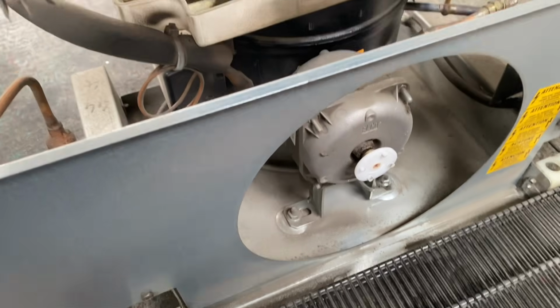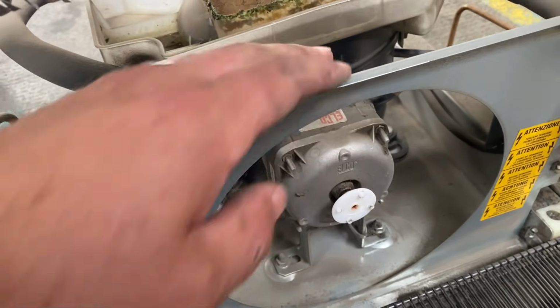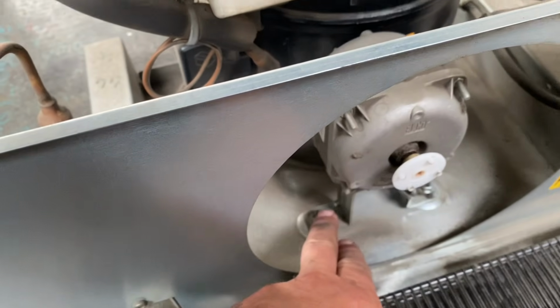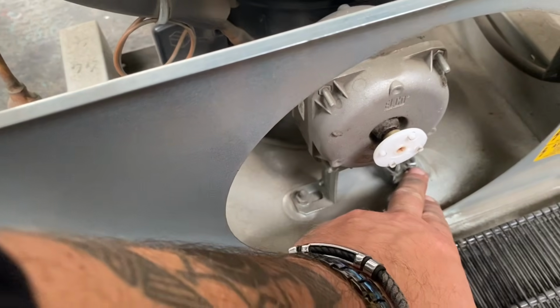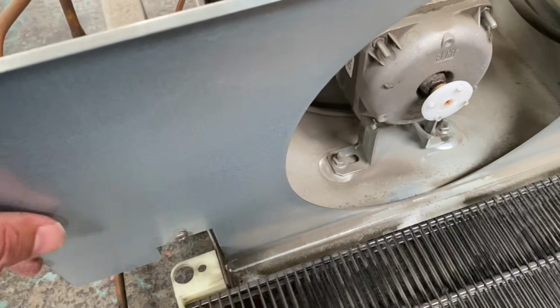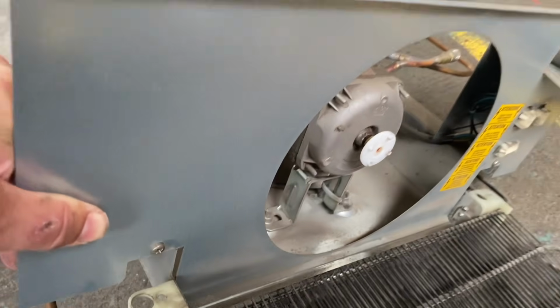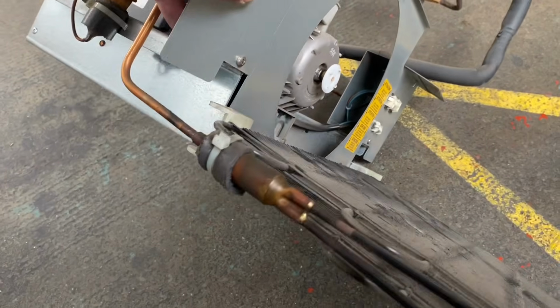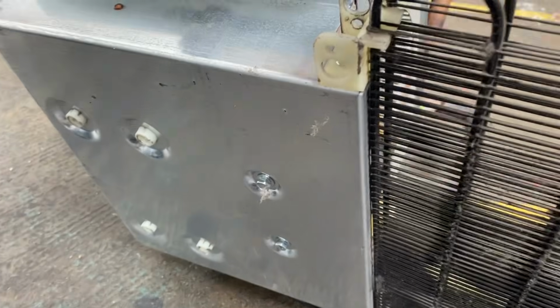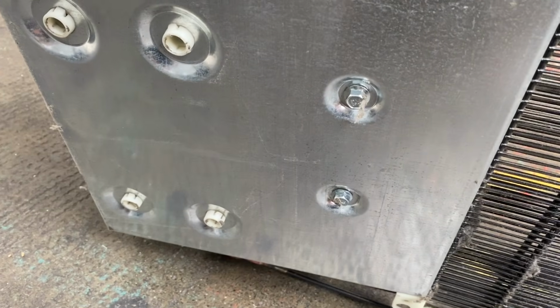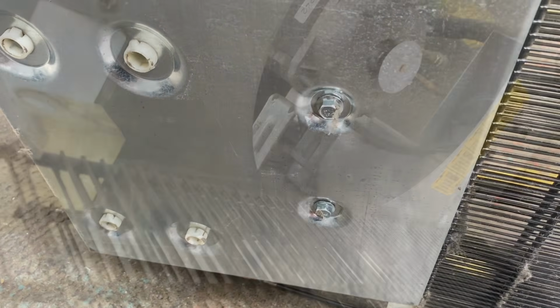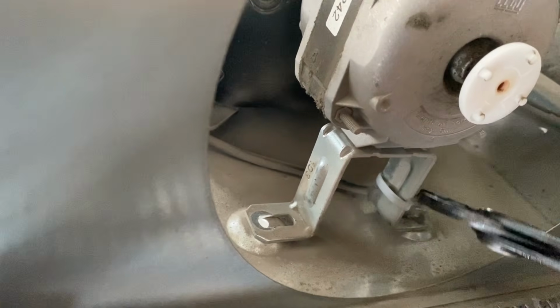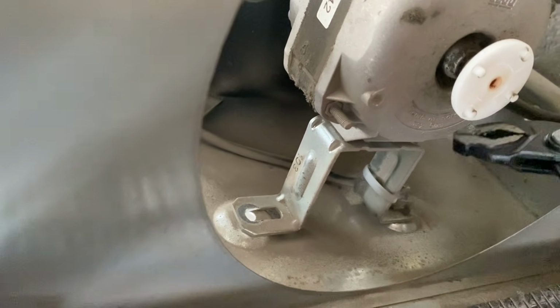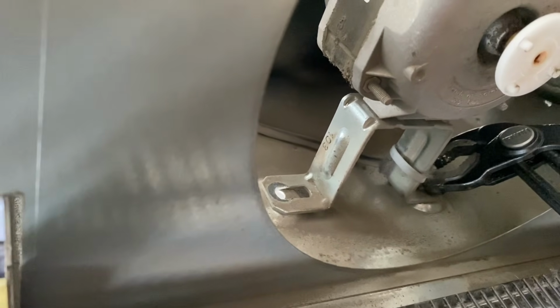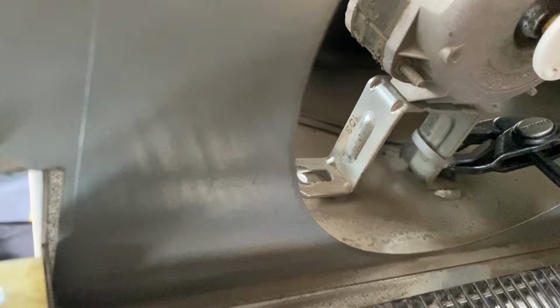So put that to one side, and then you can see this is the actual fan motor housing in place here. Now you've got to unscrew these 2 bolts. So the fan motor sits on a bracket which screws to the actual base of the chiller unit. What we normally do is tip it on its side so you can get access to both sides of the bolts, and then with some pliers or socket set or a ratchet you need to remove those 2 bolts.